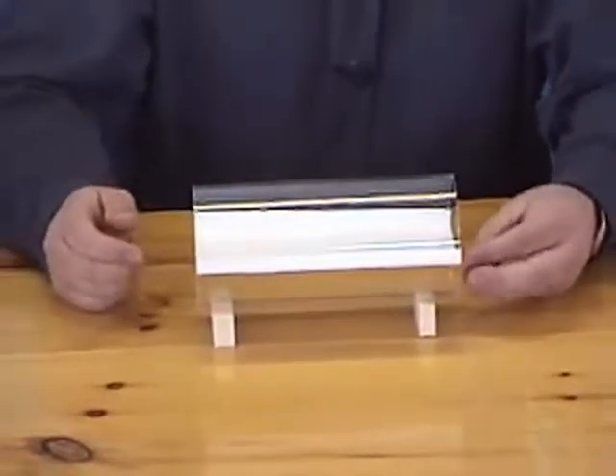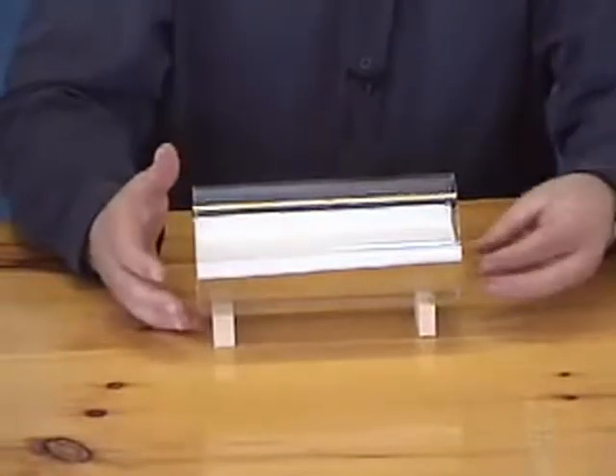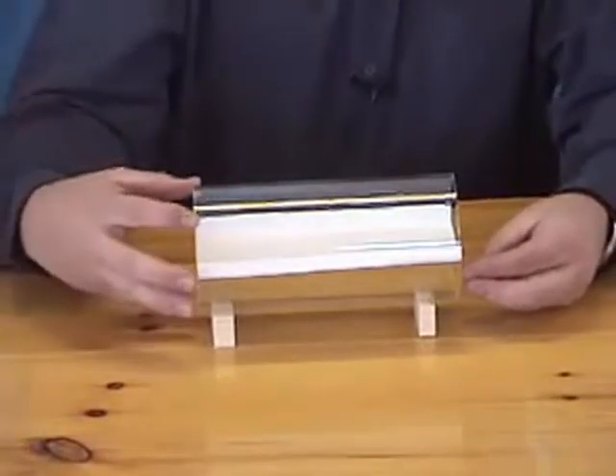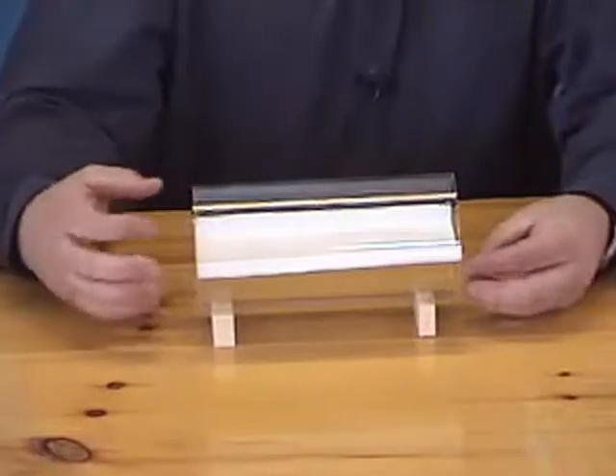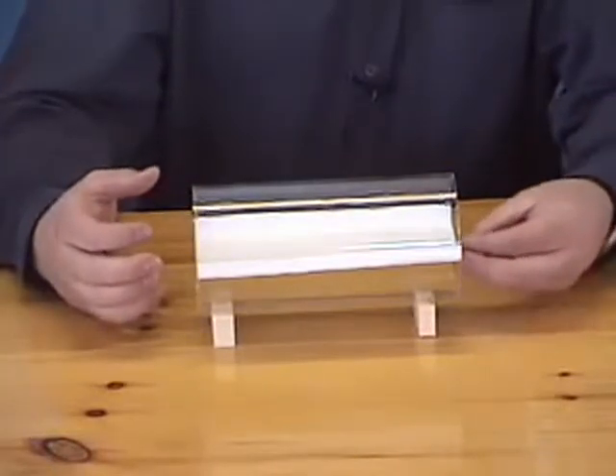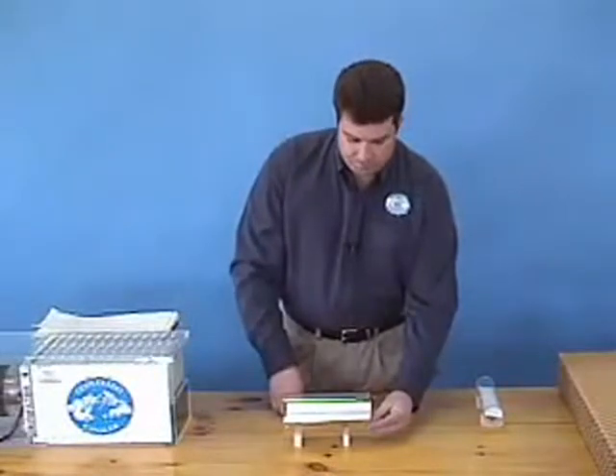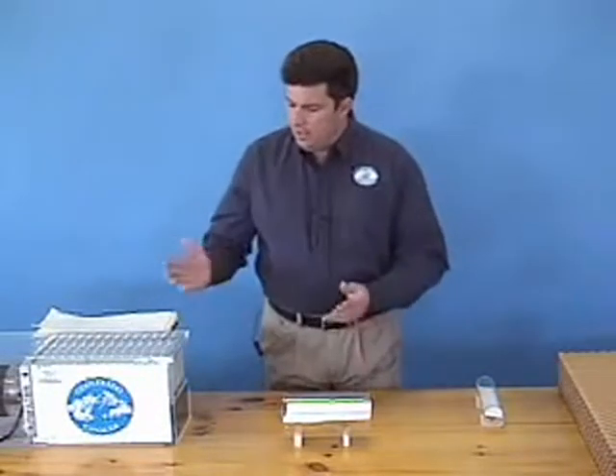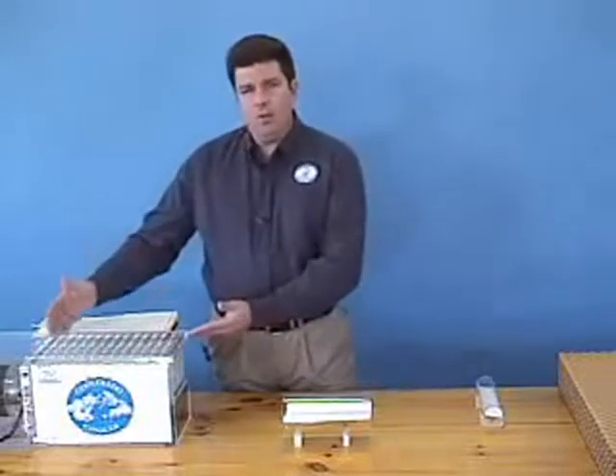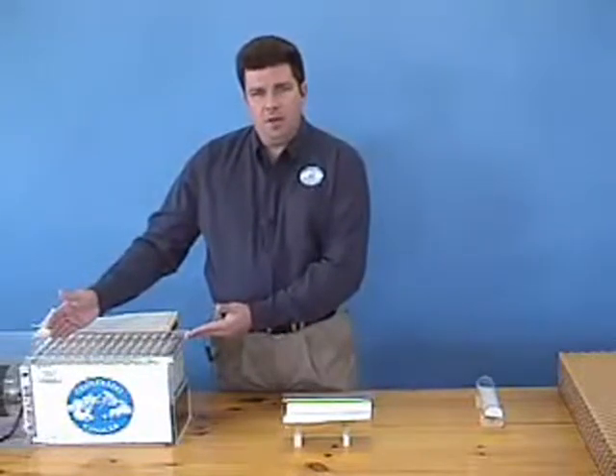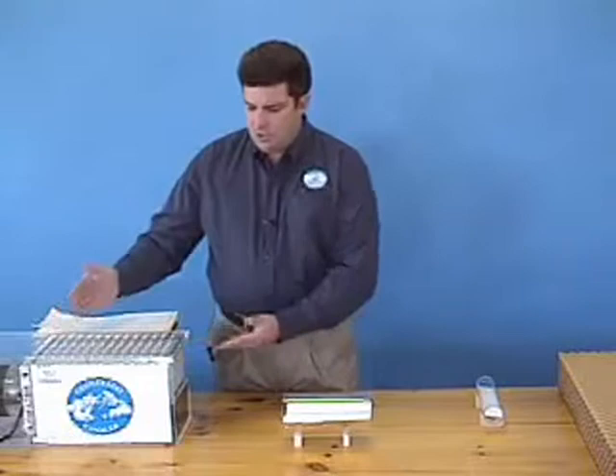So in theory, the conditioned air you get at the end of this long pipe is going to be about half the quantity of the air you started with, and it will be cooled to the wet bulb temperature without adding any moisture. But we know that Coolerado coolers can cool below the wet bulb temperature, and our theoretical limitation is cooling towards the dew point temperature of air.